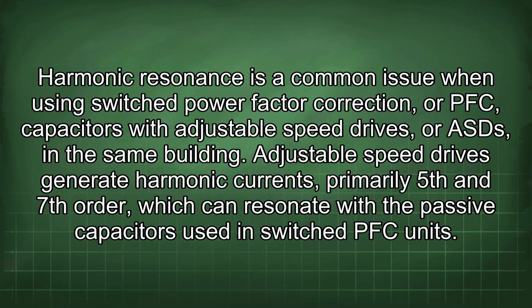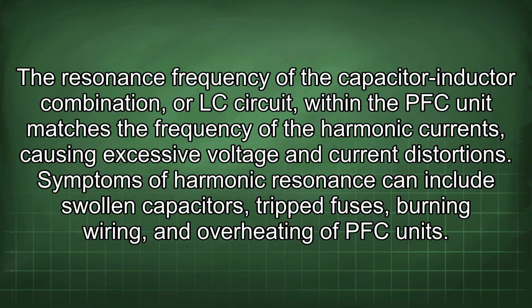Harmonic resonance is a common issue when using switched power factor correction, or PFC, capacitors with adjustable speed drives, or in the same building. Adjustable speed drives generate harmonic currents, primarily 5th and 7th order, which can resonate with the passive capacitors used in switched PFC units. The resonance frequency of the capacitor-inductor combination, or LC circuit, within the PFC unit matches the frequency of the harmonic currents, causing excessive voltage and current distortions.